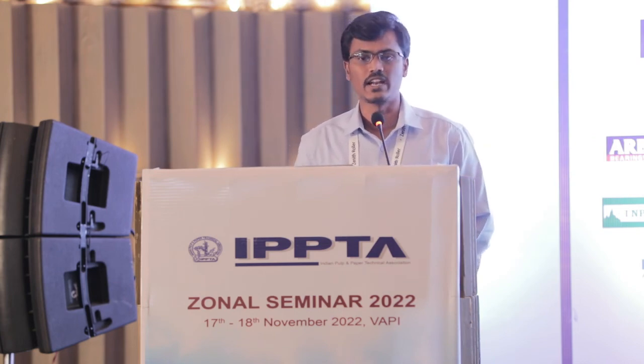Highlights shared by our peers at other events include: steam saving from a spiral heat exchanger around 25 tonnes per day; green steam generation from a recovery boiler; insulation of an indirect heater saving around 95 tonnes per day; process re-engineering in the evaporation plant achieving 5% increase in renewable energy source; digester modification enhancing fuel production with green energy — 32 tonnes per day fuel production increase and 4% increase in renewable energy. Usage of biochip to reduce fossil fuel consumption in CPP achieves around 40 tonnes per day coal reduction, and usage of biogas to reduce fossil fuel in the lime kiln achieves around 3.5 tonnes per day coal reduction.